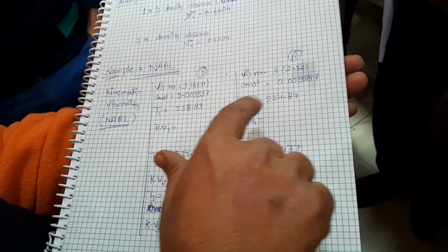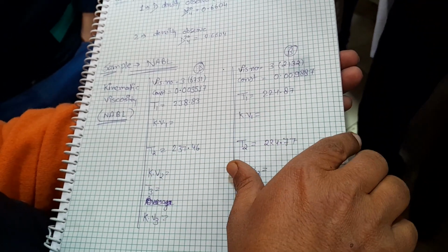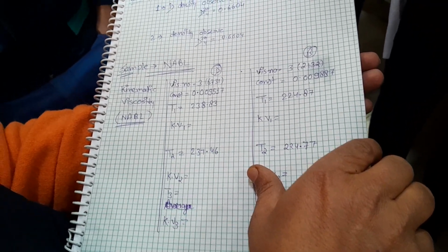With an unknown sample, it becomes difficult to select the viscometer. Sometimes, this is the experience. For example, you have a bitumen sample, and you will be asked for the kinematic viscosity at 135 degrees centigrade or 100 degrees centigrade. First you just do the pour point of that particular sample. This is the best way to decide which viscometer is required for the kinematic viscosity. Taking the sample in your hand, you can assume. So that is also experience. This is the manual method.